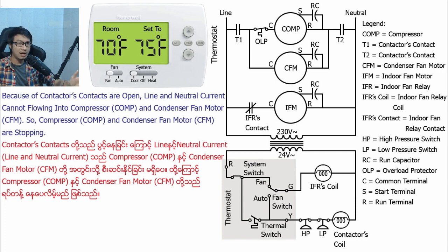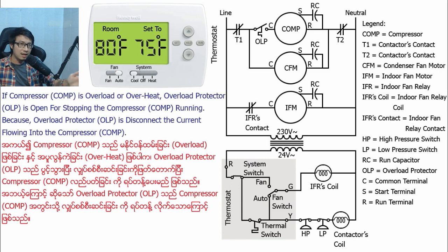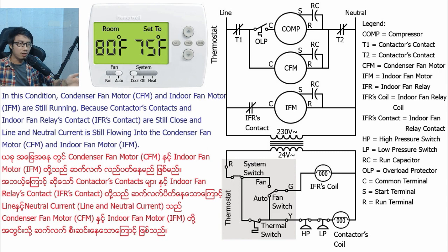If the compressor is overloaded or overheated, the overload protector opens to stop the compressor running, because the overload protector disconnects the current flowing into the compressor. In this condition, the condenser fan motor and indoor fan motor are still running, because the contactor contacts and indoor fan relay contacts are still closed and line and neutral current is still flowing into them.